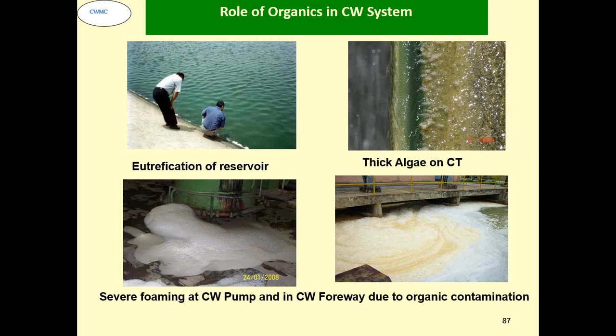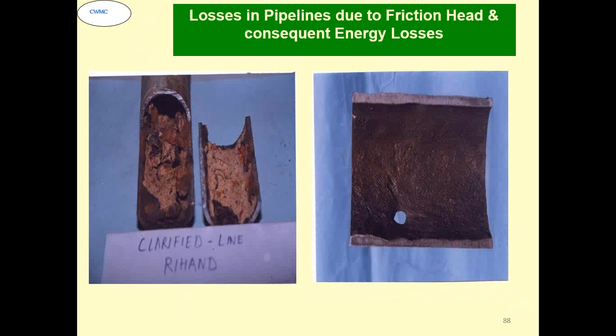Likewise, in the other two bottom pictures, you see a thick foam formed because of organic material produced from two different kinds of trees. One is the acacia tree, another is the casuarina tree. Their leaves were falling in the cooling tower and contributed to so much generation of foam, and the foam was so stable that it was not degenerating even after 24 hours. Typically you can see microbiologically induced corrosion and fouling, and below that the whole cause in the pipeline is the corrosion below the deposits.